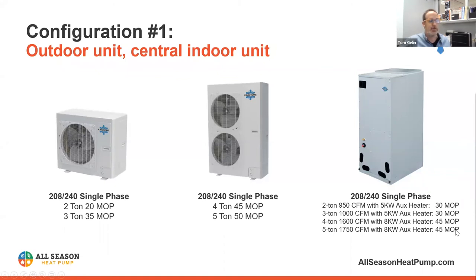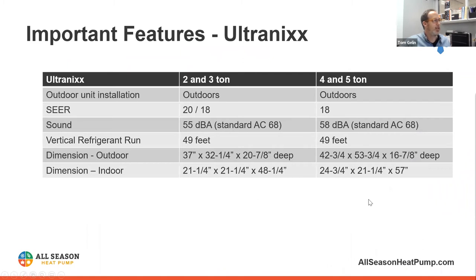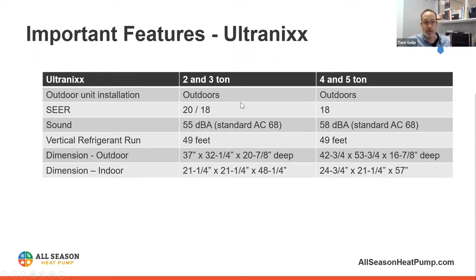This is the electrical that would be different from what we're doing with the furnace. If the electrician charges for this extra circuit, this is the size of them — it's not very big. On dimensions and refrigerant runs: KingHome does not have the longest refrigerant runs in the world — most are 49 feet. The indoor unit is not even two by two by four feet. It'll be tight fitting with a water heater, but the four and five-ton unit is a little taller. The outdoor unit is fairly small. A standard air conditioner is 68 dBA — our heat pumps are quite a bit quieter.